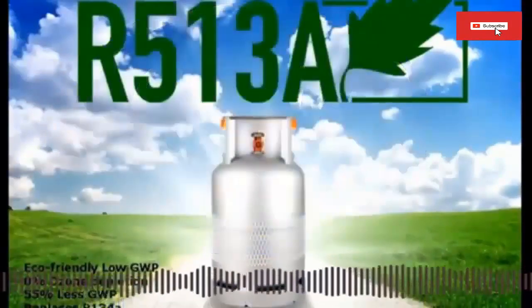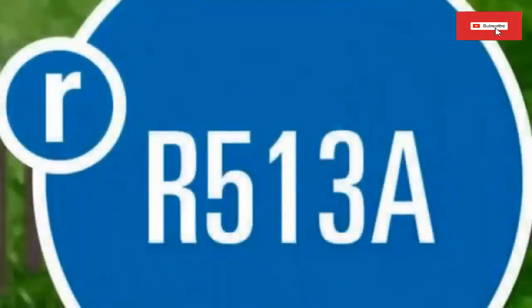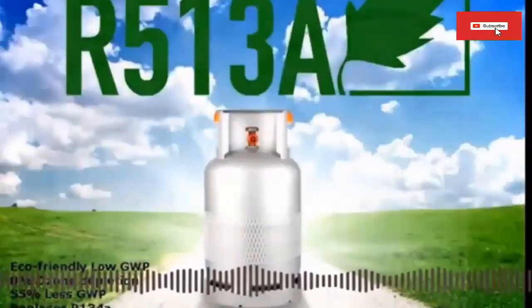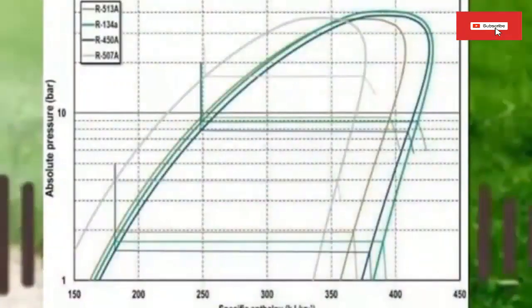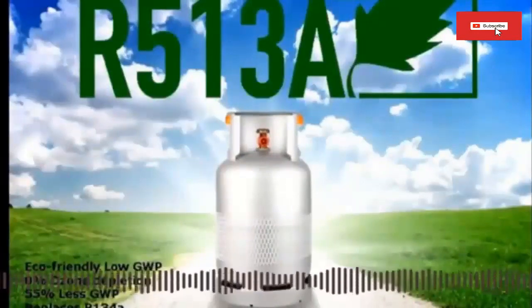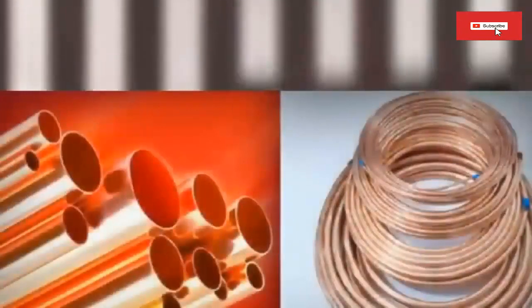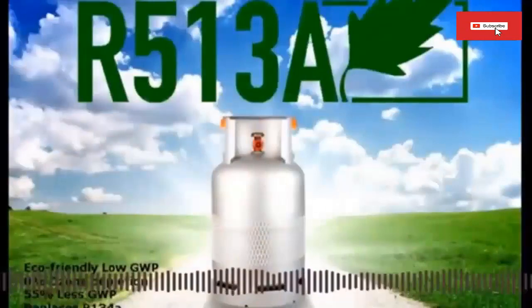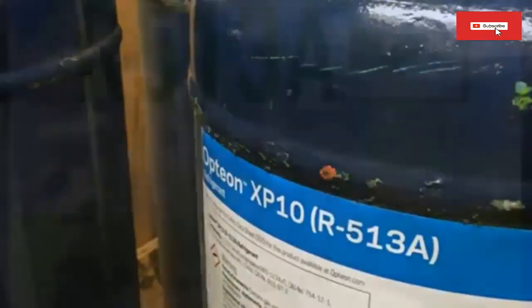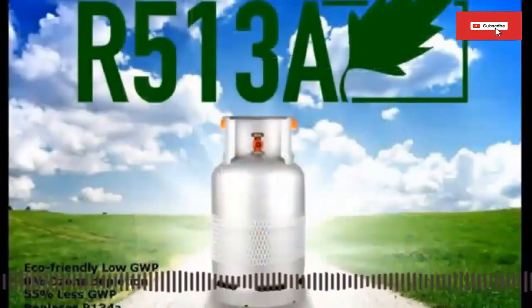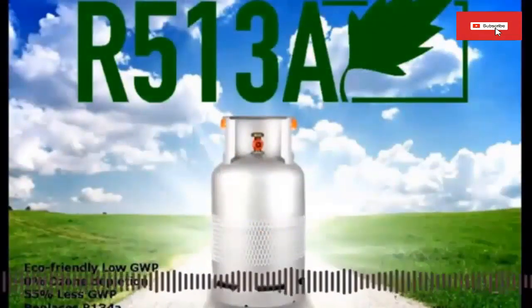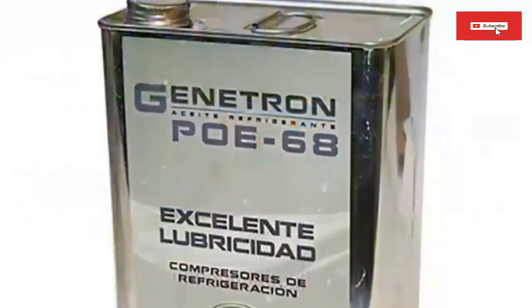11. The higher vapor density of R-513a on the suction side of the compressor results in a higher mass flow rate. 12. When using R-513a, the mass flow rate increases by about 15%. 13. Depending on the diameter of the pipes, a higher mass flow causes a significant increase in pressure drop in some lines and an increase in the compression ratio of the compressor. 14. R-513a is also known under its trade name, Opteon XP10. 15. R-513a is compatible with the equipment, components and gaskets of an existing R-134a installation. 16. R-513a is compatible with POE synthetic oils.